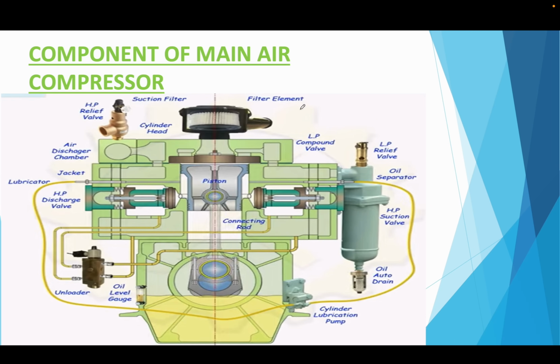Now this is a tandem type air compressor. The suction is coming from here, it is going to suction here, the discharge is coming from here, it is getting intercooled. This is the intercooling happening here. After that it is entering the suction valve here, and then it is going to second stage compression. Coming out from second stage compression here, discharge is happening here. Then this is the aftercooling happening, and now it is discharged. So in tandem type, the air is flowing like this. This area is the intercooling area, and this area is the aftercooling area.